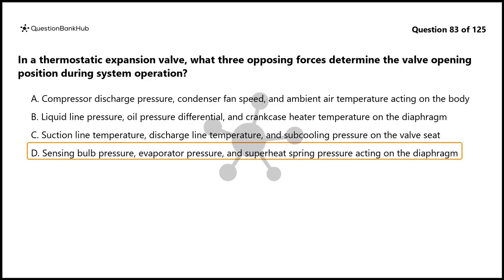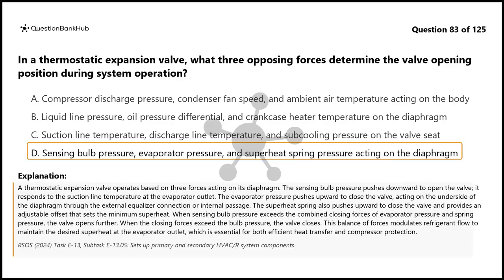The correct answer is D. A thermostatic expansion valve operates based on three forces acting on its diaphragm. The sensing bulb pressure pushes downward to open the valve. It responds to the suction line temperature at the evaporator outlet.